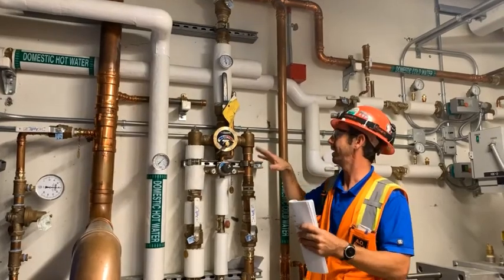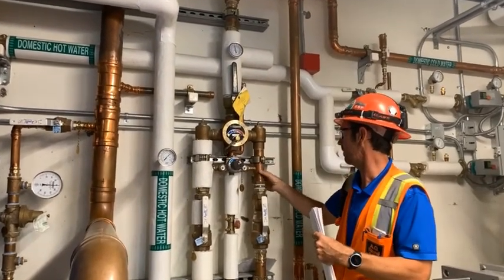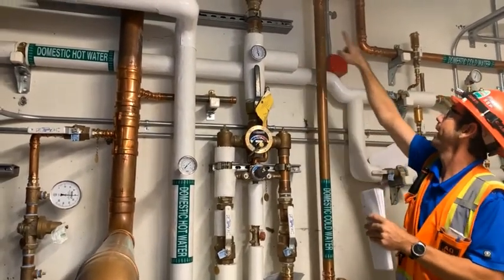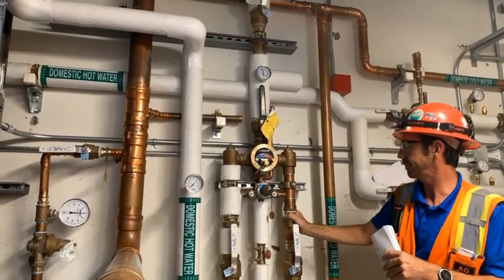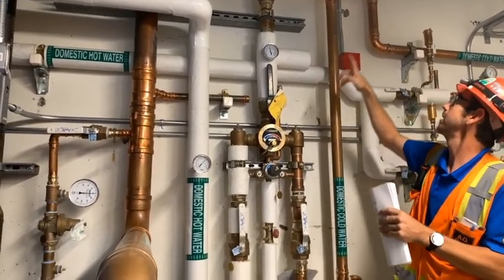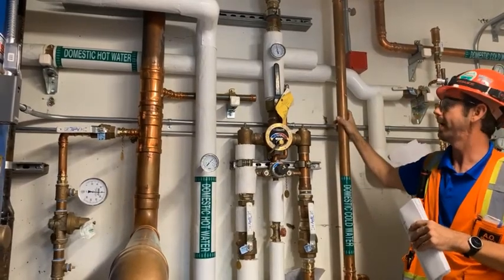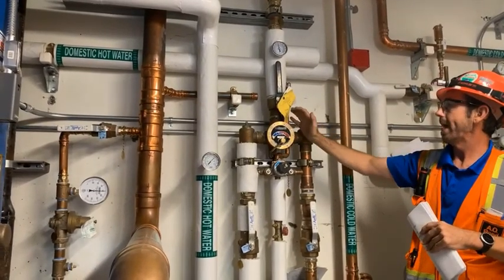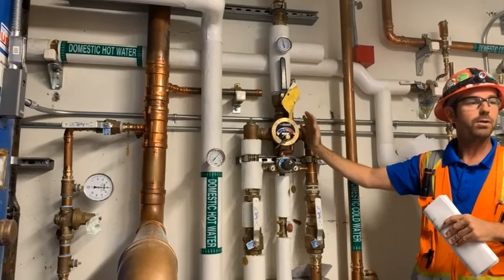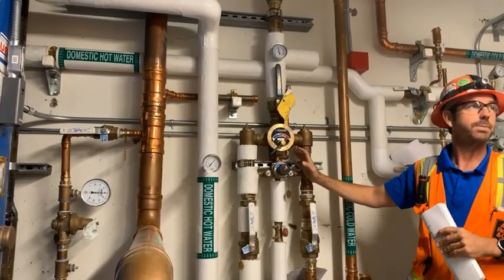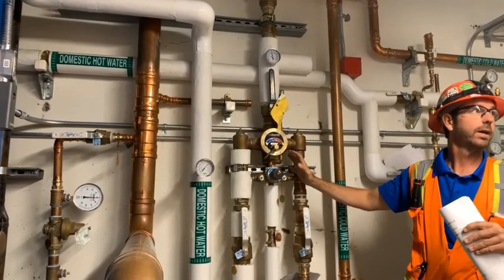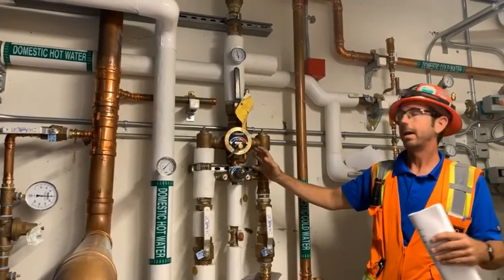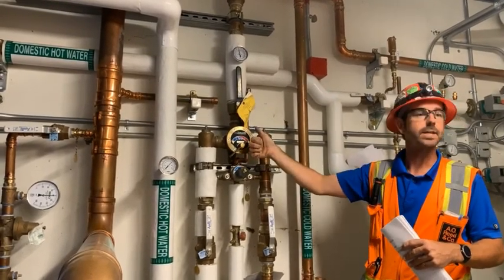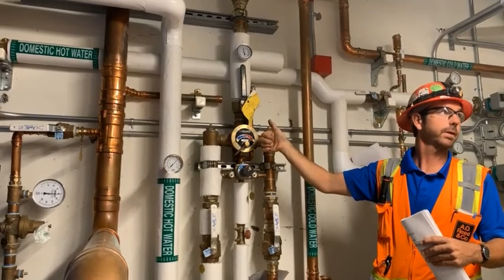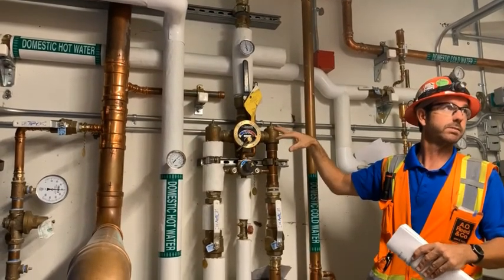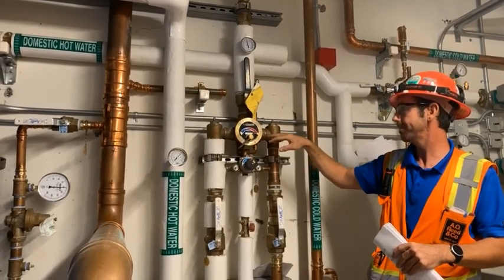We're switching over in between kind of a hot and a cold system. The cold water will branch off here and feed the mixing valve. It also branches off and it feeds the heat exchangers behind me. Right now I have both valves set at the maximum outlet temperature of like 124, okay? I don't want any higher than that for burning. And then from that point, we've set it down to a 120 leaving temperature, okay? So the leaving temperature on both valves is 120.